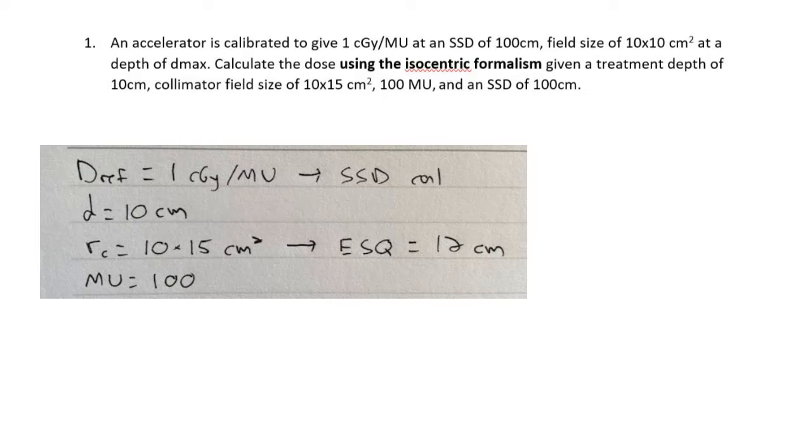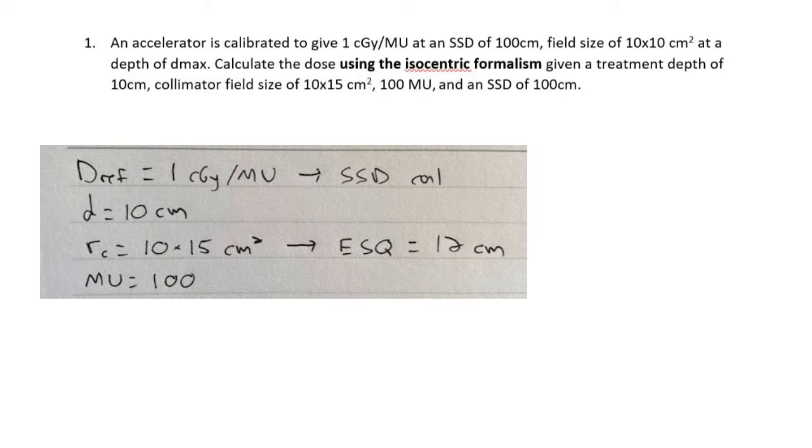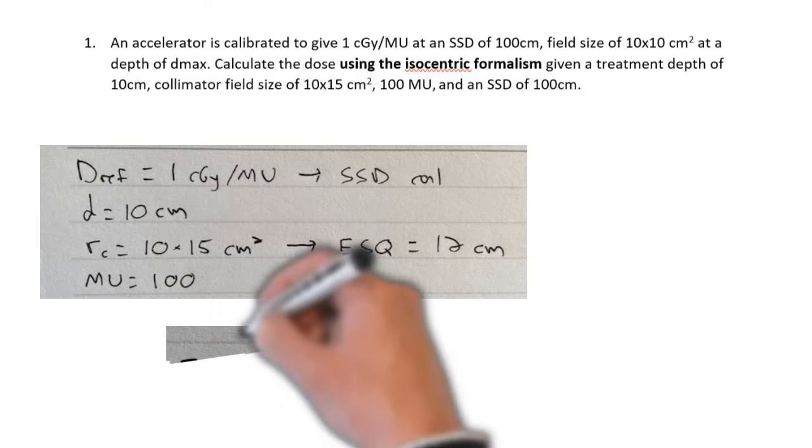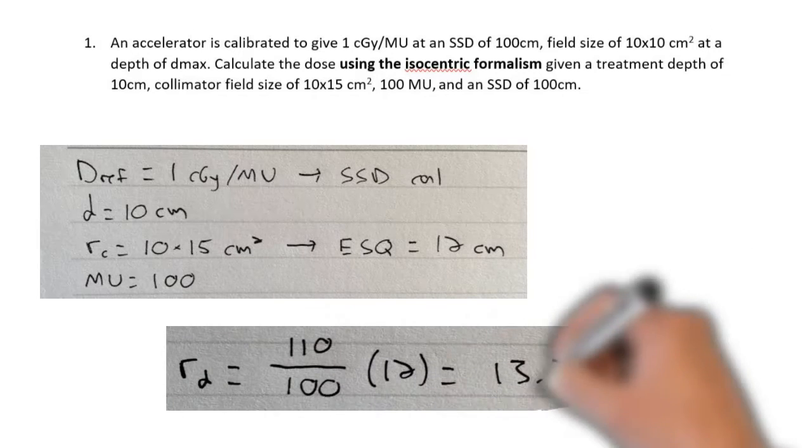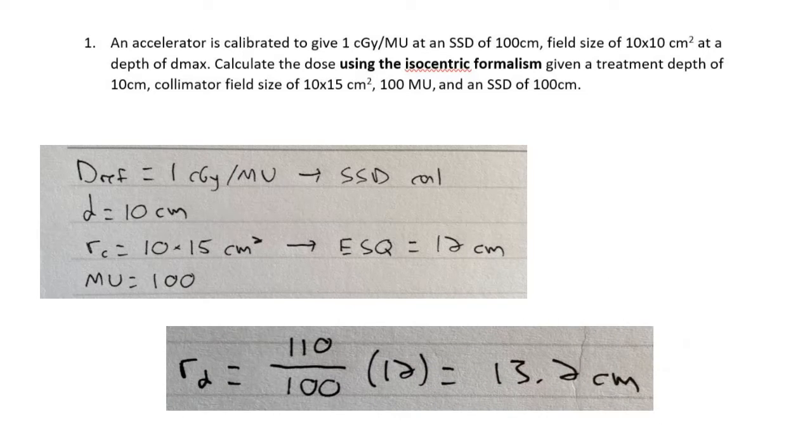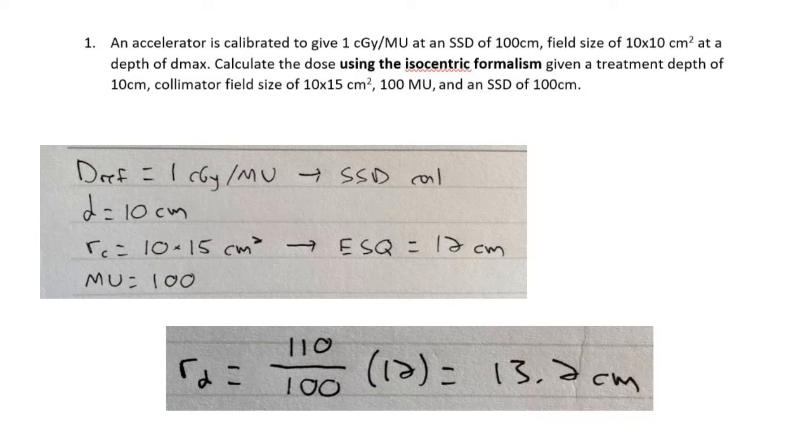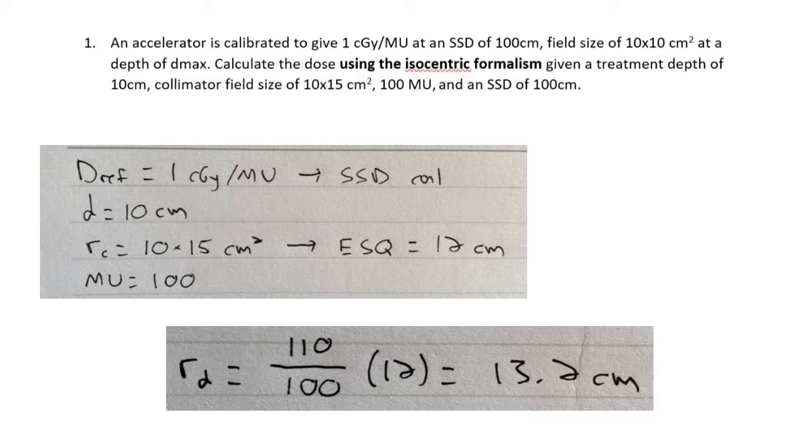There's one thing right off the bat that we need to calculate: the field size at the depth of the calculation. Remember our depth is 10 centimeters and our SSD is 100, so we are actually 110 centimeters away from the source. We need to use beam divergence here, and this here is the equation that we can use to calculate that field size. We just take our calculation distance of 110 and divide it by the source to isocenter distance of 100 and multiply by the field size - that's just a similar triangles argument there - and we get a field size at depth of 13.2 centimeters, which we will need to use later on in the calculation.